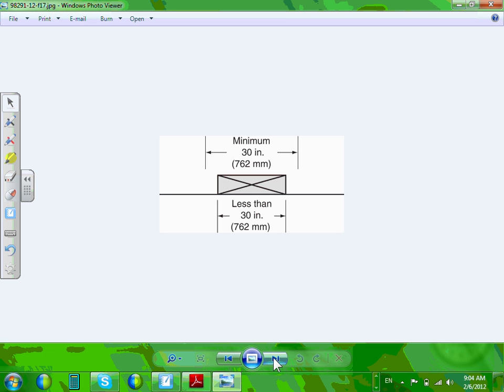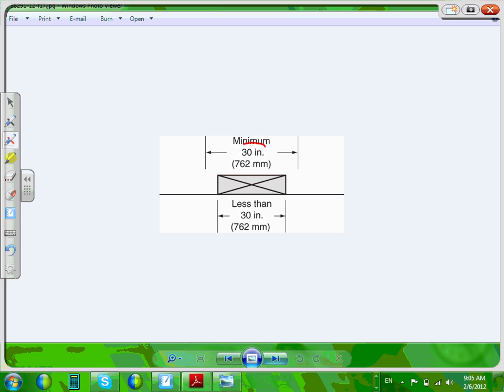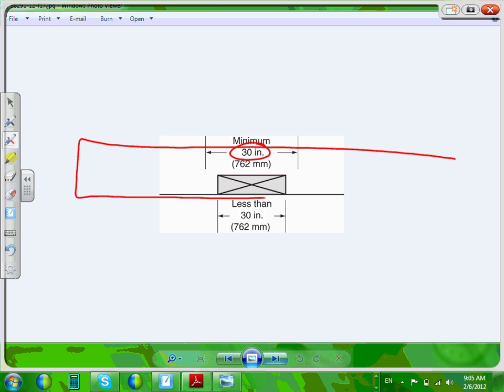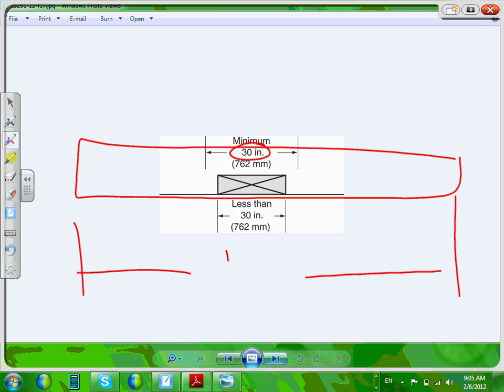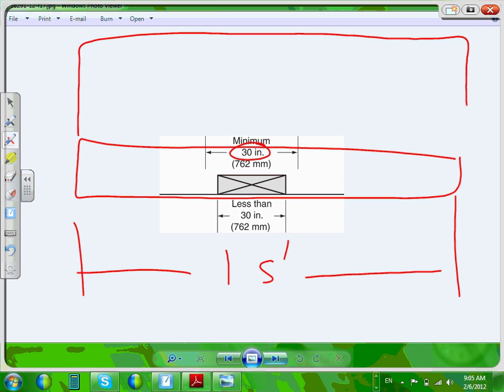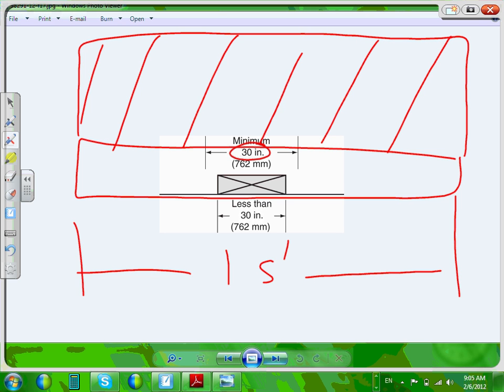Okay, working space, the width. The width of the working space is always 30 inches or the width of the equipment, whichever is bigger. I have a 20-foot switchgear, so the width of the working space must be 20 feet. If I have a 20-inch wide panel, then I have 30. Does that make sense? So the minimum is 30, or the width of the equipment. If I have a panel that goes all the way up to here, and from here to here is 15 feet, what do you think the working space in front of it is going to be? It's going to go all the way to 15 feet. The width of the equipment or 30 inches, whichever is bigger. Not 15 feet back, no, just the width.